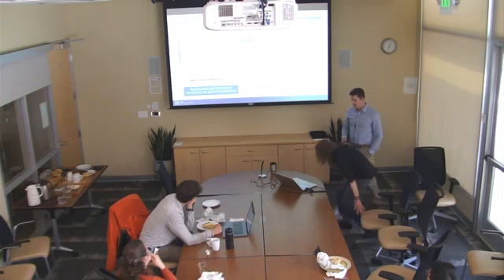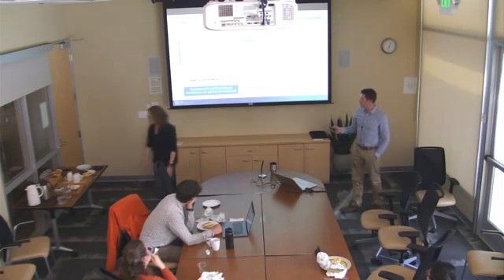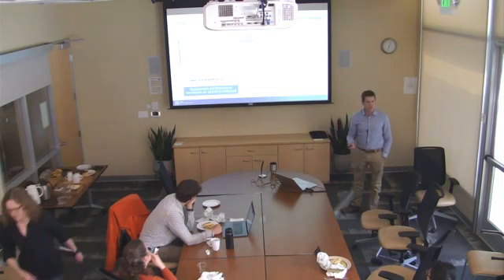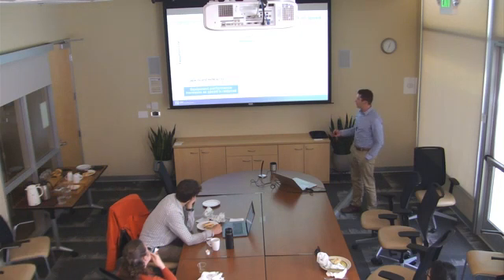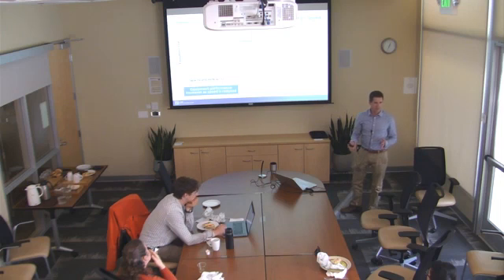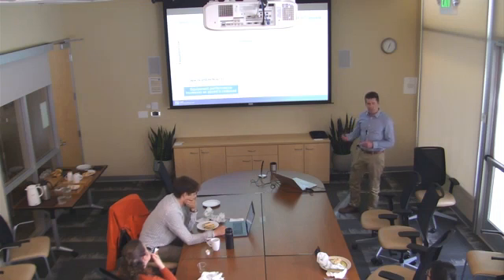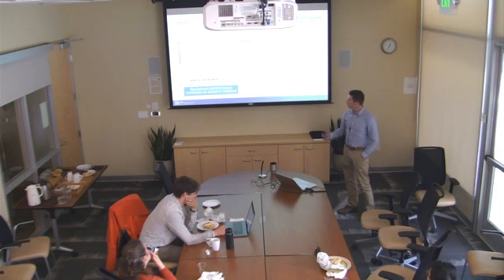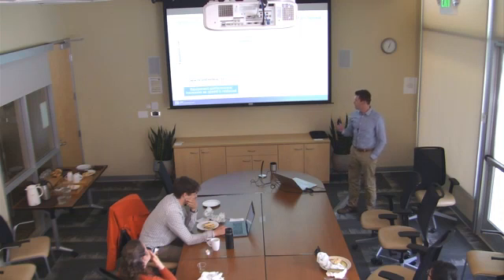Okay, so here's kind of the first set of results. This is looking at the equipment performance, so this is not including the ducts. It's just how the equipment performs. The DOE rates all these systems. If you're familiar with SEER ratings or EER for air conditioners, this is kind of similar to that. So it's just looking at the box. And what you see is that as speed is reduced in variable capacity systems, the performance improves significantly. And then as outdoor air temperature rises, the performance of the equipment goes down.